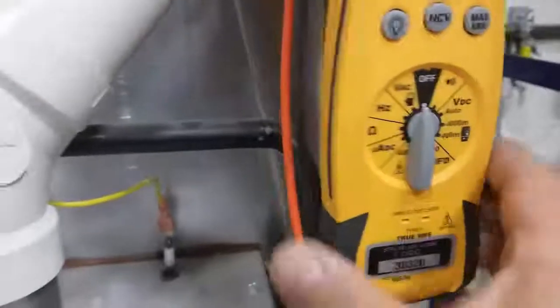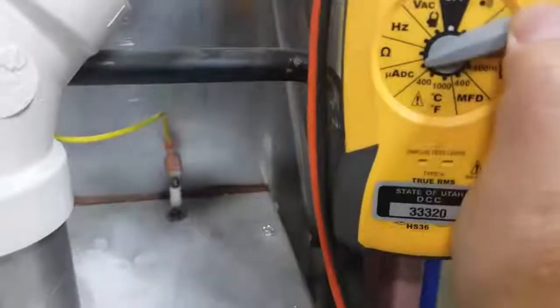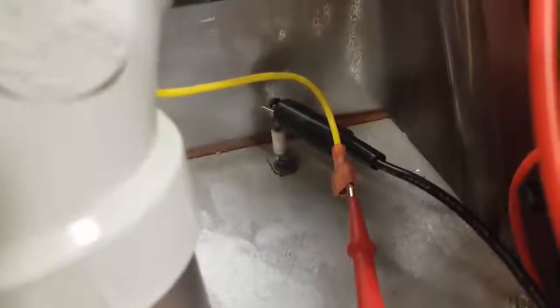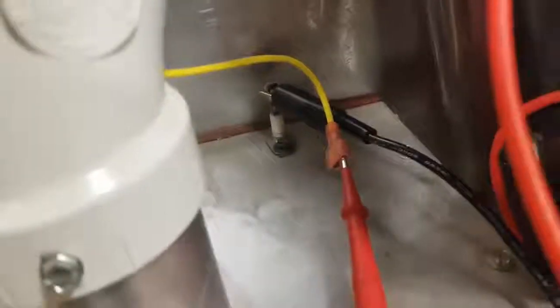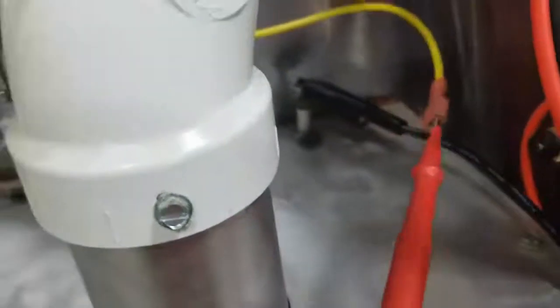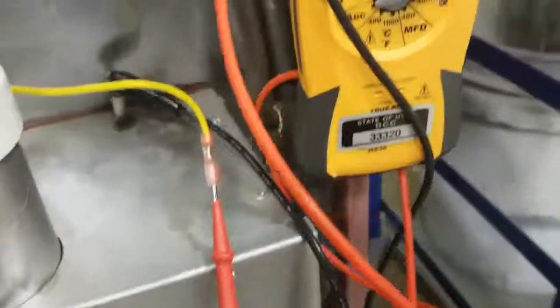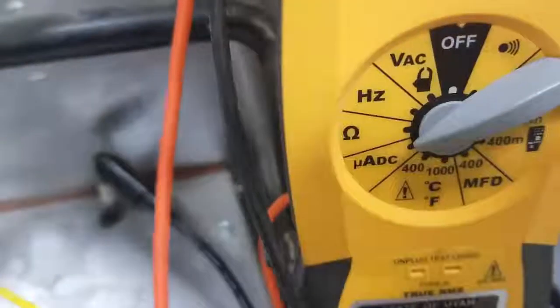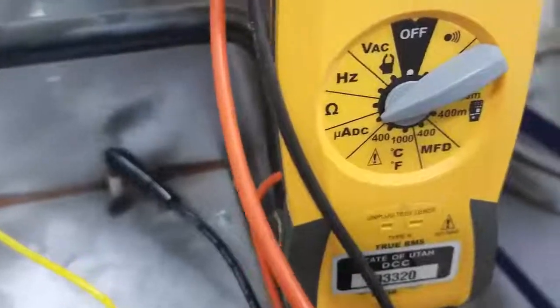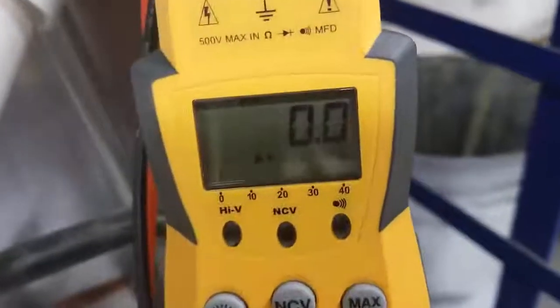Okay, to check for flame sensing the old way, you need a meter that you can set to microamps DC. The flame sensor's right here, it has one wire connected to it. We unhook that. So I've unhooked my flame sensing rod from the flame sensing wire that goes to the circuit board. I put my meter in series, so I hooked one lead to the wire, and the other lead, the black one back there, is hooked directly to the flame sensor. I set my meter for microamps DC, and now I'm just going to flip the furnace on, call for heat, and we're looking for anywhere from 2 to 4 microamps for a good strong flame signal.